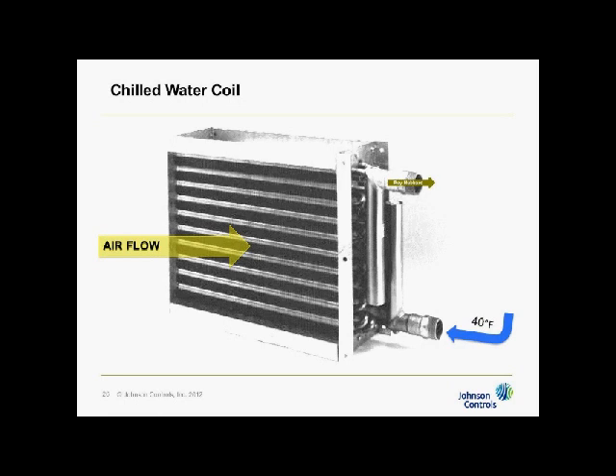How it works is there's, on the other side, in the leaving air side of this coil, in the back where you can't see, I have a temperature sensor that might be set for 55 degrees Fahrenheit. I'll talk all in Fahrenheit, in IP units. 55 degree Fahrenheit. The air enters the coil at roughly 80-67 and leaves about 55, 54.9, using the 40 degrees water that comes out as 56. That's how it works.